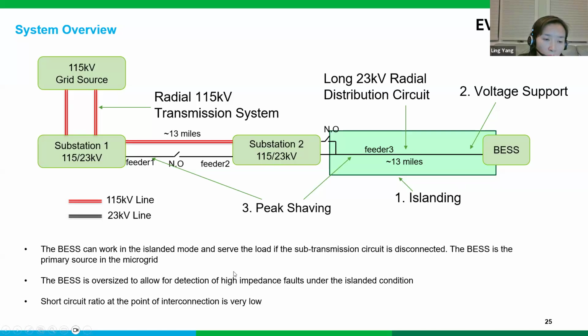When we design the battery, we intentionally oversize it to allow for fault detection under islanding conditions. So the size of the battery is higher than the peak load of the island. Also, given the point of interconnection is really far away from the substation, the overall short circuit ratio at the point of interconnection is very low. So it connects to a very weak system.